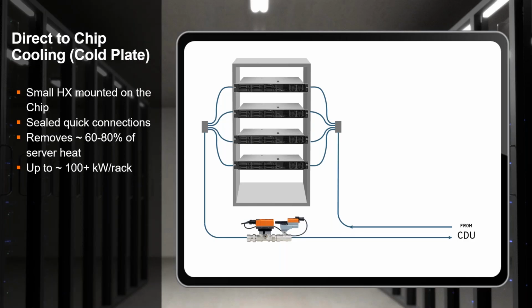Now, do I think in the future we could use AI and other smart things to predict the changes that were coming and proactively make changes in flows and things like that? I think that's a very real possibility. But today, we're usually going for a single flow. What's pictured there is the Belimo EPIV, and we love this product in this solution because you can program it for a specific flow rate. You can network that guy, and so if I need 22 gallons a minute for those 4 servers today, that valve's going to give you 22 gallons a minute all day, every day going through there.